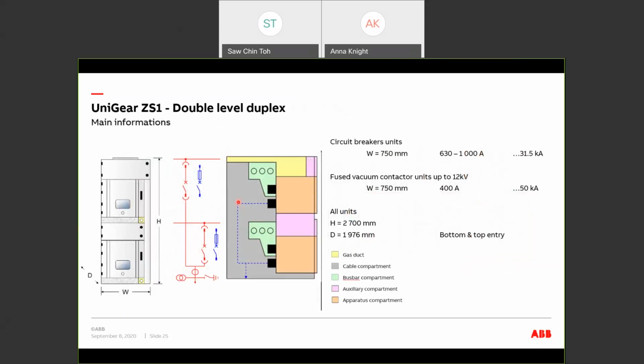Another way we could configure these double level panels is to make them duplex panels. The layout of the panels is pretty much the same as the double level, but sharing the same cable termination. So if you can see, 2 of these breakers or contactors are sharing the same cable termination. So of these breakers, one of them will be the main and the other becomes the reserve. Due to the application that we commonly see for this type of panels, we only offer up to 1000 amps, 750 millimeter wide panels only.